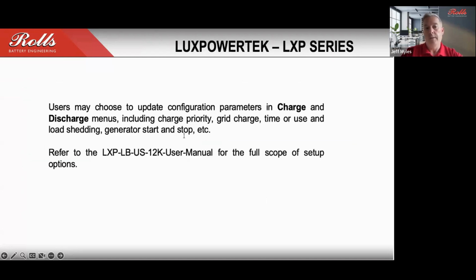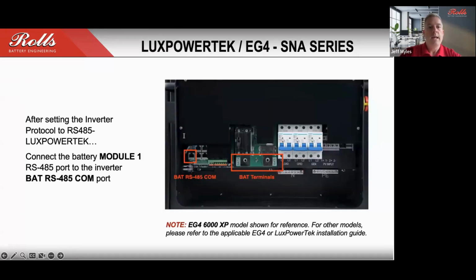If you have, we've included this in the manual as well, any other charge discharge parameters, grid charge, time of use, things like that, all of those settings will be outside of this guide. So that's at your preference and how you set that up. And then walking through, we explained where the terminal connections were, which one of the ports is going to be set up for communication. In some cases, they may not be clearly marked on the inverter, and we did notice that as well. So we wanted to identify this is a particular port that you want to connect to.